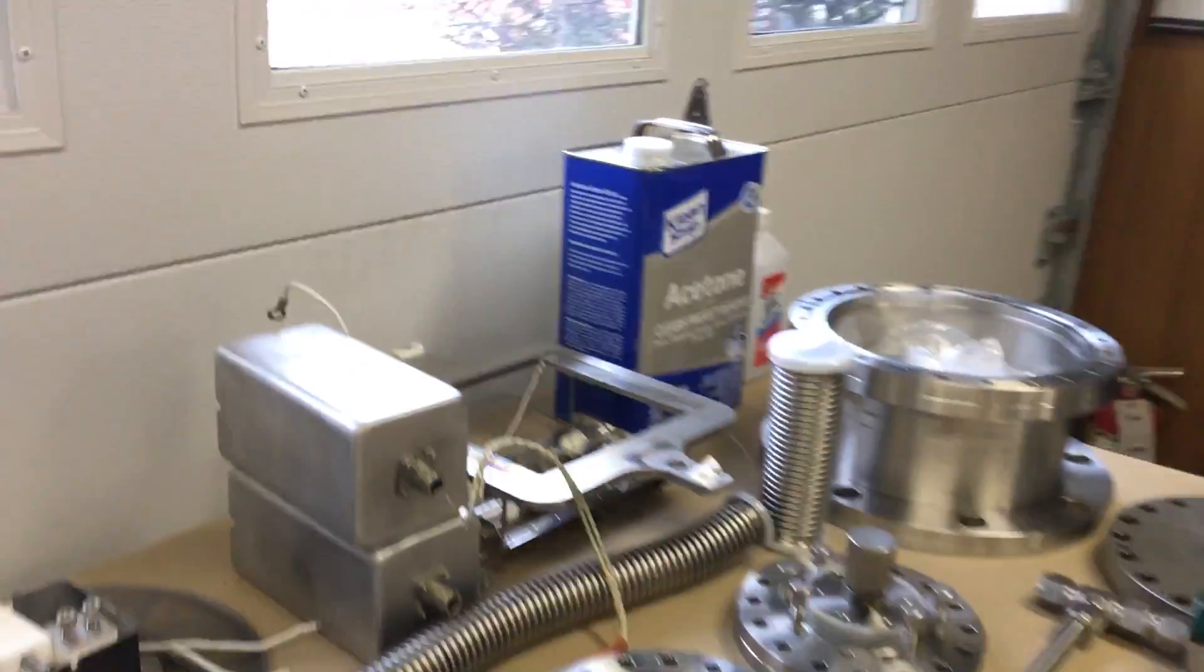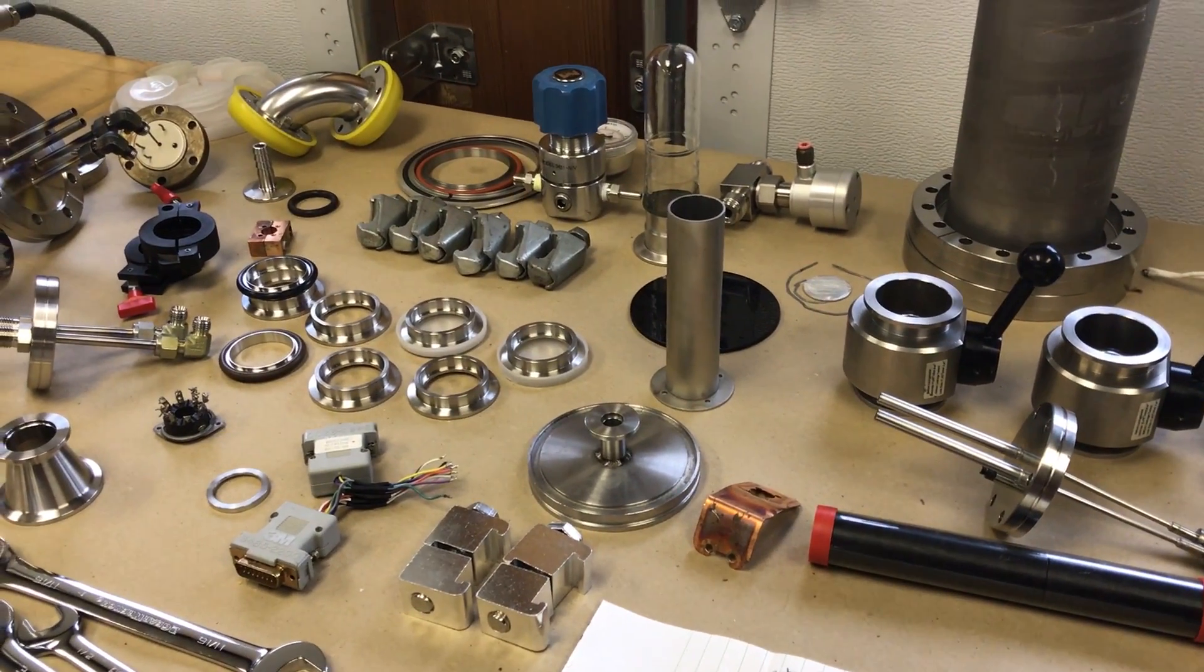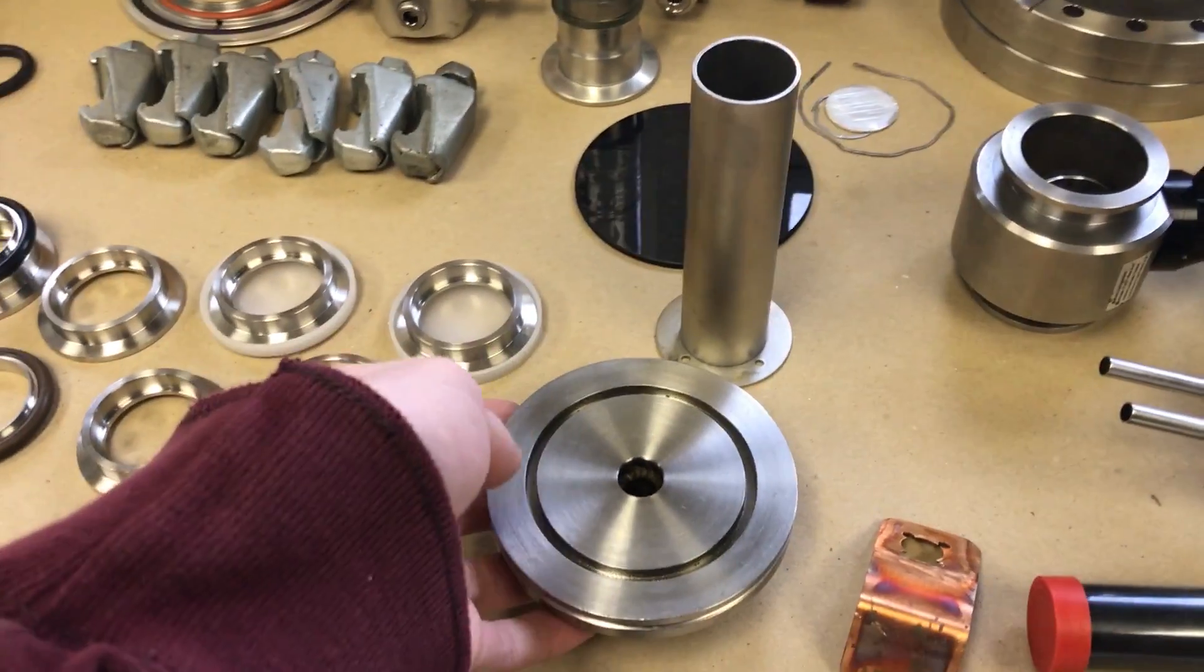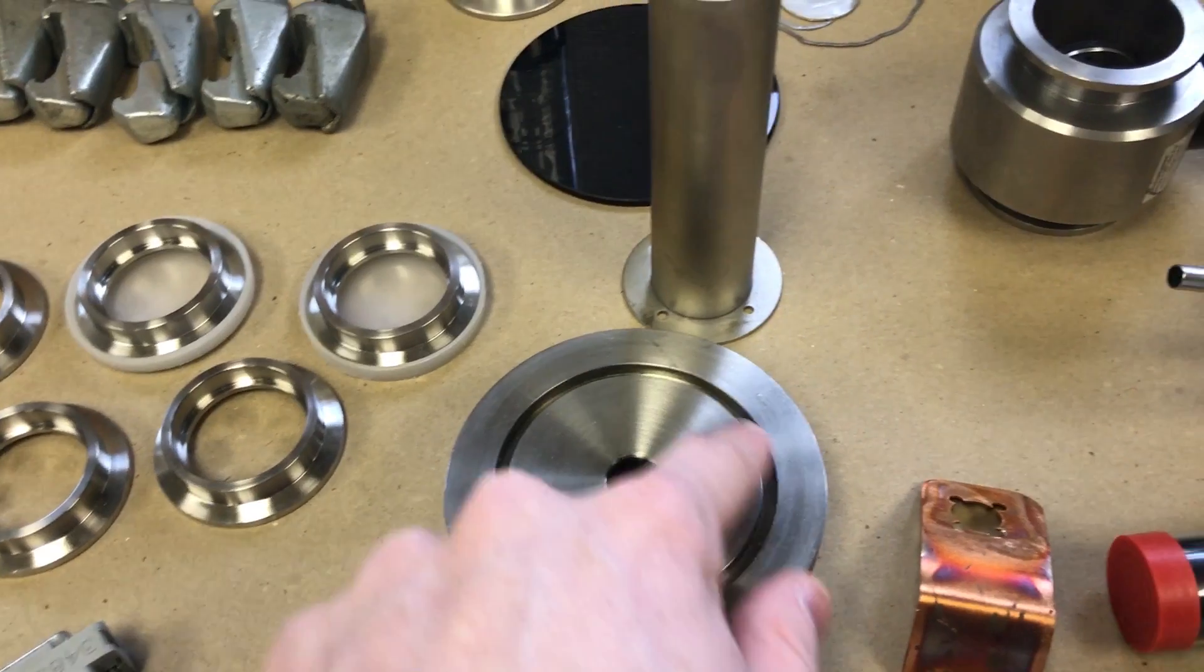So then there's ISO seals, which are not quite as good as the conflat because they use a gasket. So here, this is an ISO-K. There's ISO-F, which is the same thing, but instead of using clamps, it uses through-hole bolts. So the ISO has a flange that has a groove in it, and there'll be a centering ring assembly.